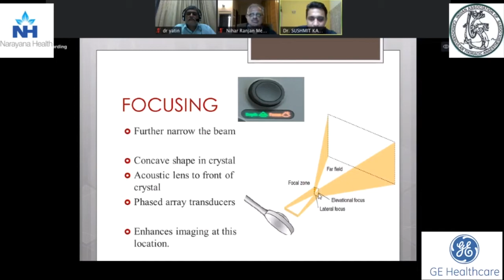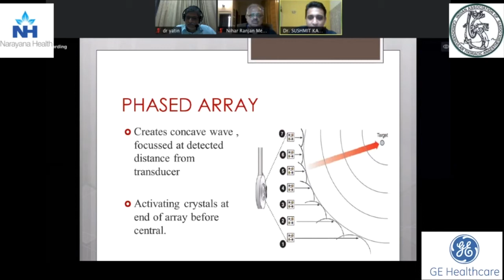And how is this focusing done? It is done by the use of phased array crystals, in which instead of having a single crystal, there is an array of crystals in a linear fashion, but instead of activating all of them at once, the crystals at one end are activated before the central ones, so that the beam does not go in a linear fashion, but is directed towards a particular target which can be better visualized. So getting a narrow beam, keeping the structure in the near field, and focusing, all three help us to improve the resolution of an image.